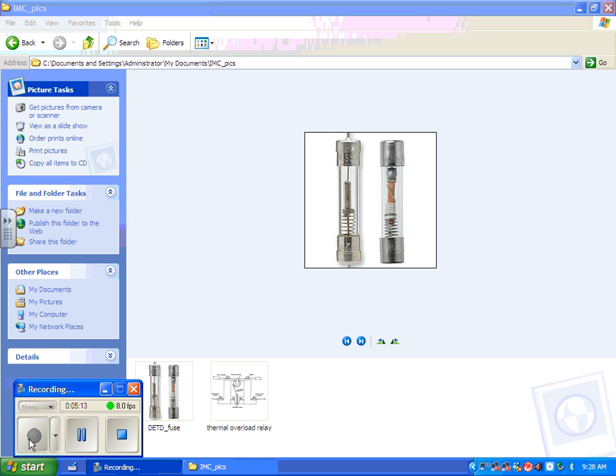Motors that are stamped 1.0 service factor, that means you cannot overload that motor at all. Don't do it. Because of that, most of the overload heaters are set to shut the motor down at about 90% of its full load amperage. We don't want it going to full load amperage. We want it falling short of that, because even at 90% it's going to let it go past a little bit, right? We don't want it going much past that, because that motor will become damaged very quickly. Then there are motors that have a service factor of 1.15. That means generally you can overload them about 15%, even on a long-term basis, and it won't kill the motor.